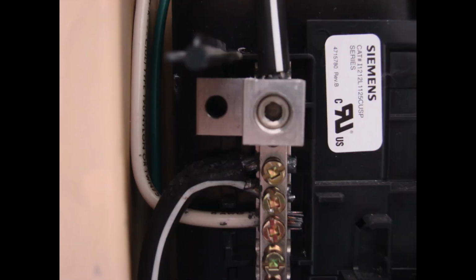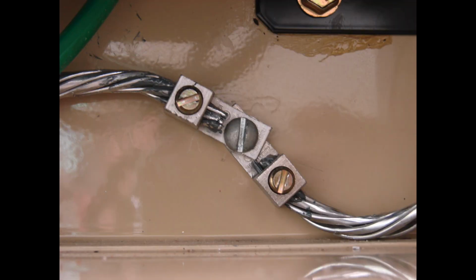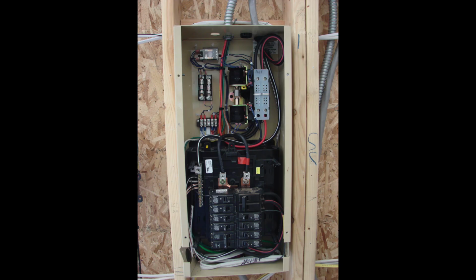Now in this transfer switch area, of course, we're going to be attaching the neutral wire that comes from the generator and the neutral wire that comes from the service panel, the main electrical service panel. There are also connections for your grounding. Of course, we need to ground the enclosure here. And you can see not only do we have the ground wire from the generator, but we also have the ground wires that are going into 2 separate lugs that are joined together for the sub panel feed that goes out and the supply that comes from the main panel.